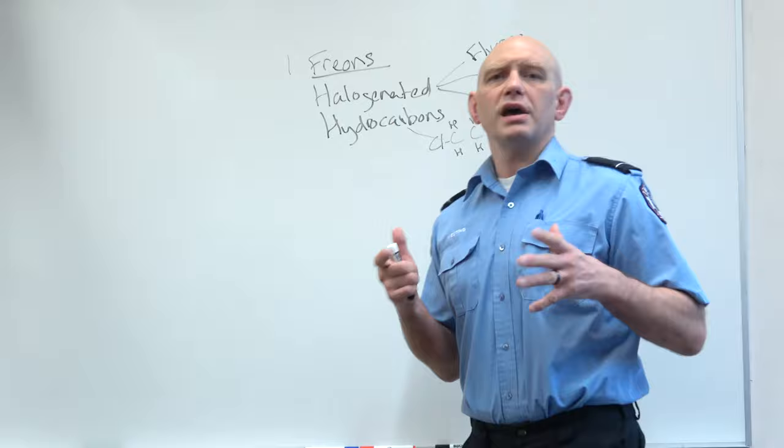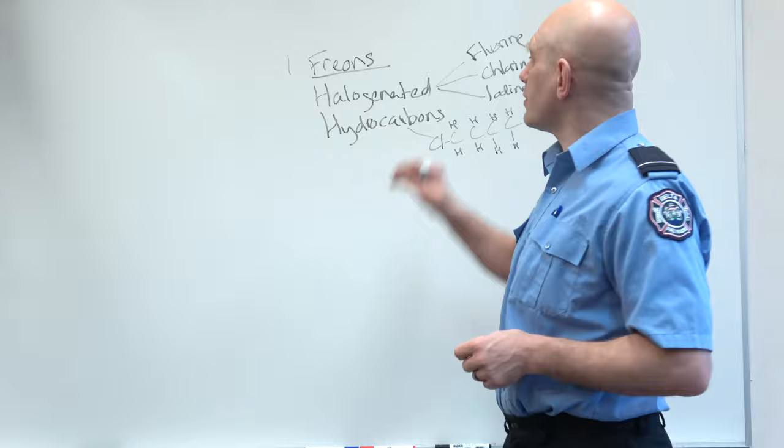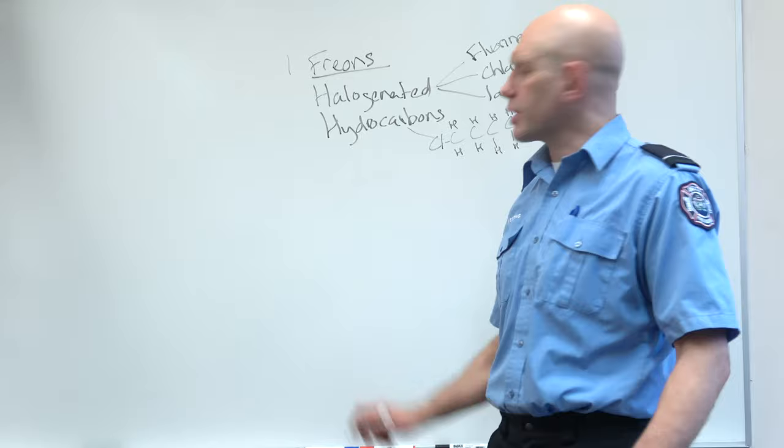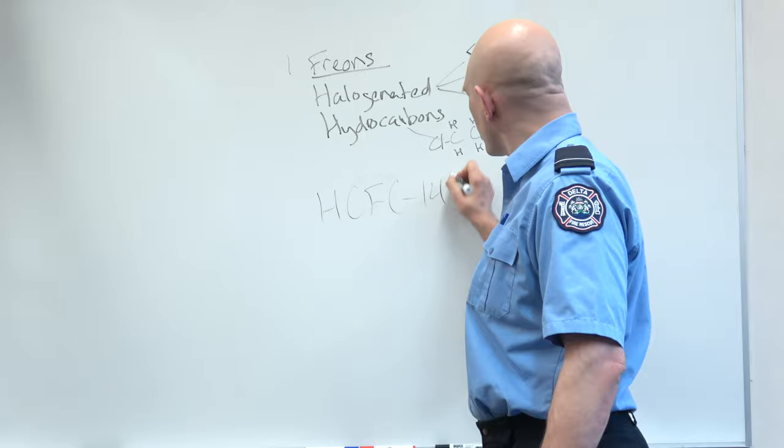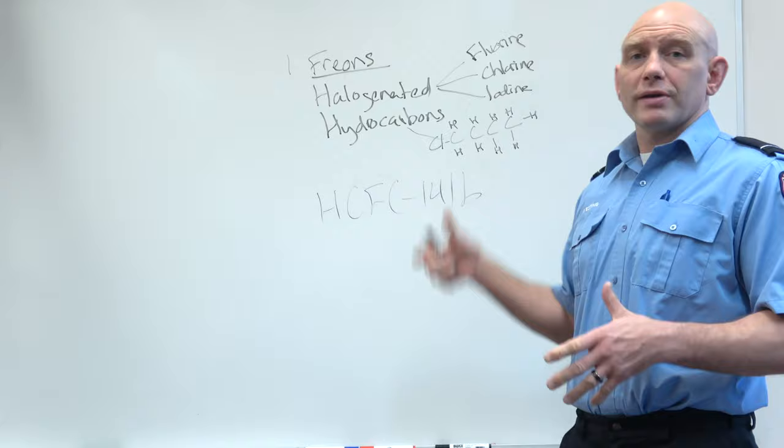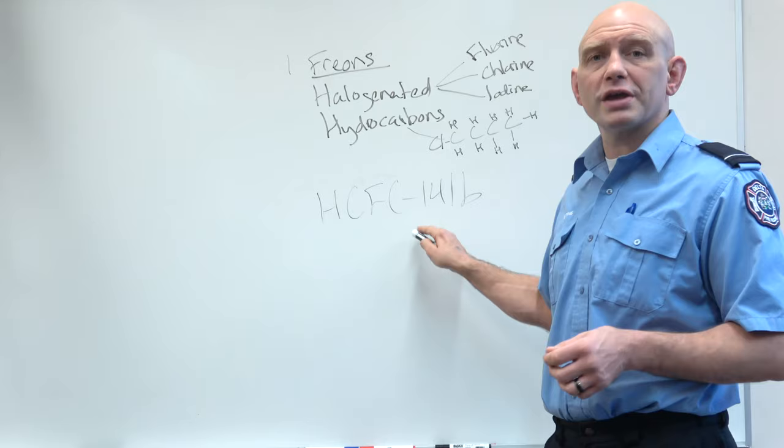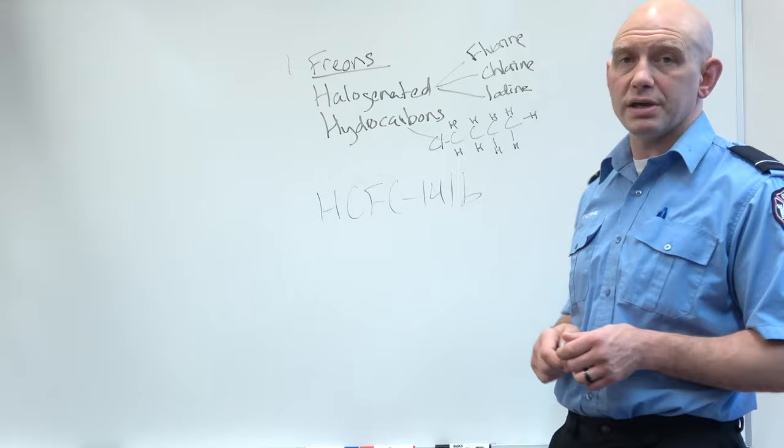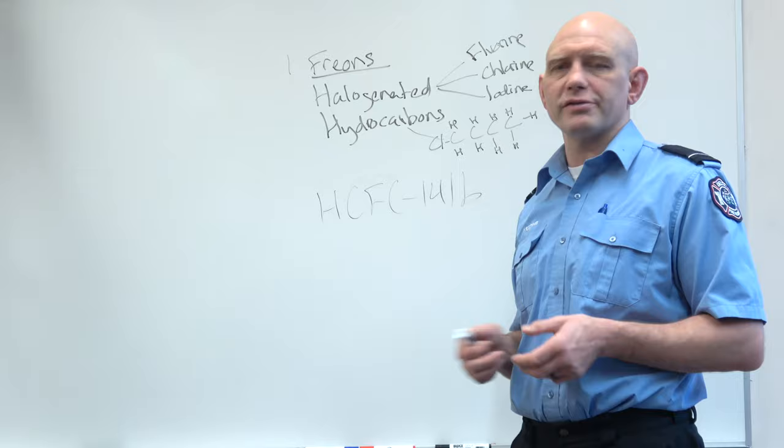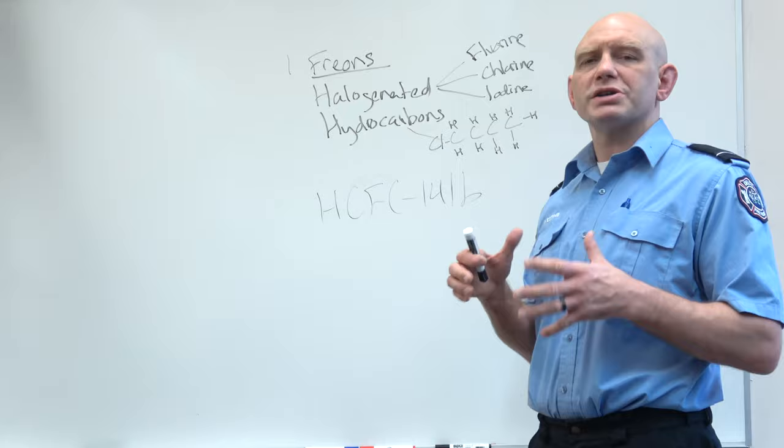That's usually the biggest hazard. But there are hundreds of Freons. Many, many Freons. Every Freon out there will have an R number. This isn't an insulation value. This is an identifier for what that chemical is. So if we go to a call and the refrigeration tech says, we had a great big leak of HCFC-141B, this doesn't mean anything to us until we look it up. We can find the MSDS for HCFC-141B. That'll tell us how flammable it is, whether it's heavier than air or lighter than air. Hint, Freons are heavier than air.